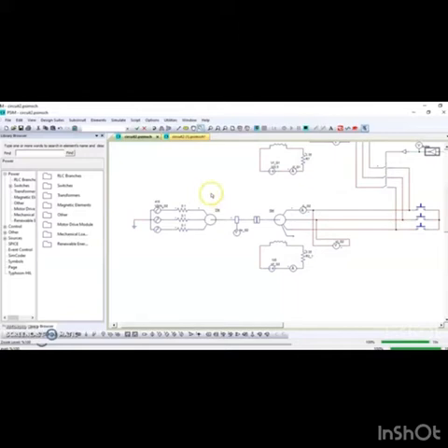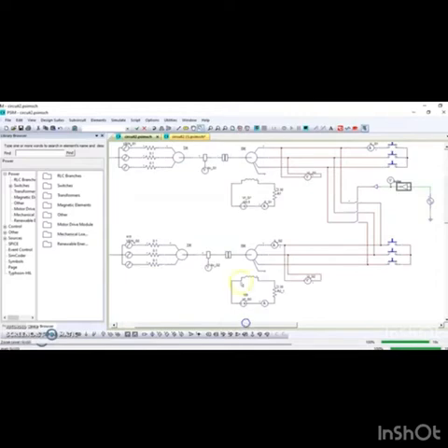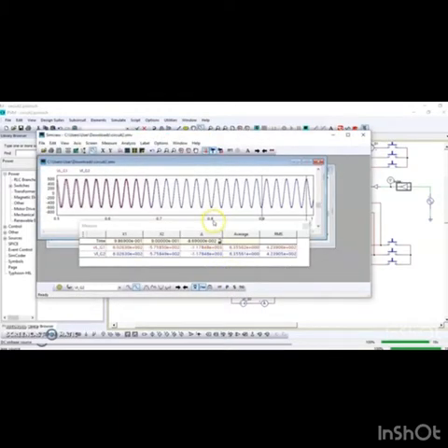Secondly, when it operates in the phase condition, generator 1 and generator 2 must have the same phase. Finally at 0.1 second, both of the generators are connected in parallel operation, which produces in phase waveform. The frequency of generator 1 must be slightly higher than the frequency of generator 2.